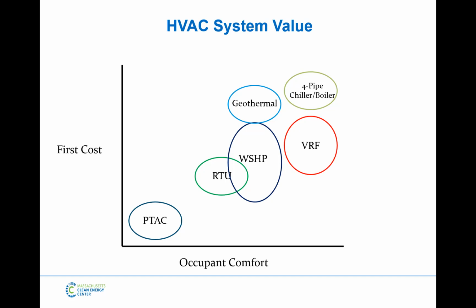If someone comes up and says, yeah, I'm looking at rooftop units, water source heat pumps, 4-pipe chiller boiler, then everything's all in the same ballpark. That's where the different benefits of flexibility and installation are going to sway what's more cost effective. But if I'm going to make some generalizations, we're going to have similar efficiency, similar occupant comfort, and similar levels of flexibility to a 4-pipe chiller boiler system. And I typically find that on most buildings we do around here, VRF has a first cost advantage. When I say most buildings we're doing around here, I'm talking about buildings under 200,000 square feet, which lines up with what JS said about a couple hundred tons.